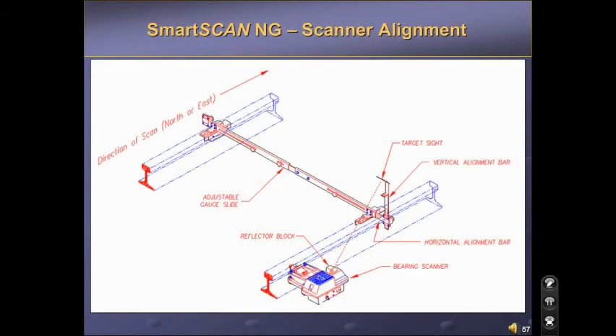Ensuring that the scanners are in the correct position is very important to the system. Alignment could affect the levels of temperatures that the system reads. First, mount the alignment fixture on the track, on the center of the transducers. When placing the alignment fixture on the rail, use the open side of the fiberglass channel as the mark. Then, using the same triangulation method used to place the scanners, make sure that the alignment fixture is square on the track. Insert the target sight into the alignment fixture and place the mirror block on top of the scanner.